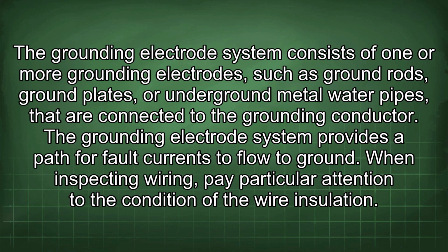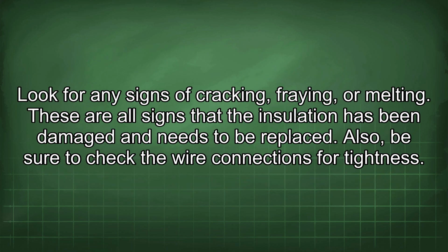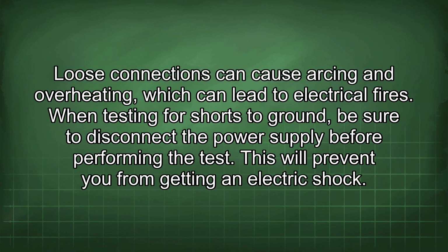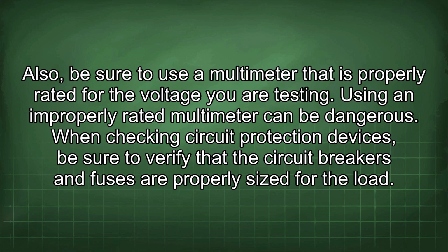When inspecting wiring, pay particular attention to the condition of the wire insulation. Look for any signs of cracking, fraying, or melting. These are all signs that the insulation has been damaged and needs to be replaced. Also, be sure to check the wire connections for tightness. Loose connections can cause arcing and overheating, which can lead to electrical fires. When testing for shorts to ground, be sure to disconnect the power supply before performing the test. This will prevent you from getting an electric shock. Also, be sure to use a multimeter that is properly rated for the voltage you are testing. Using an improperly rated multimeter can be dangerous.